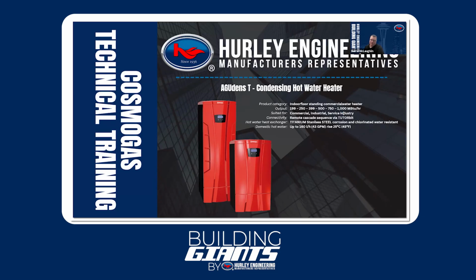Some jurisdictions have CSD1 requirements, like to see BTU values under 400 or a 399 and under 200 or a 199. So for that reason, CosmoGas made a separate heat exchanger that's a 199 version, and we can stack two of those and have a 399. It's not the exact same heat exchanger, just derated to be sold for this particular purpose. It is physically different in characteristics.